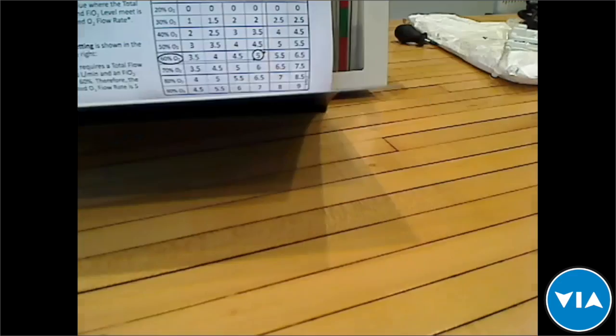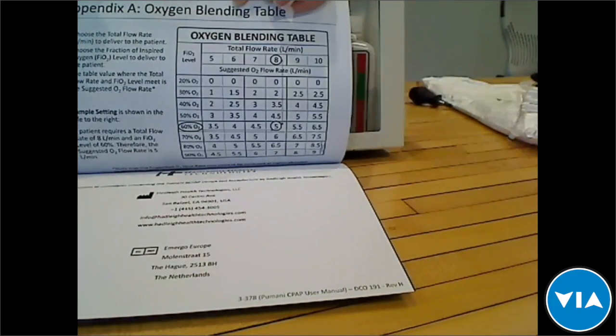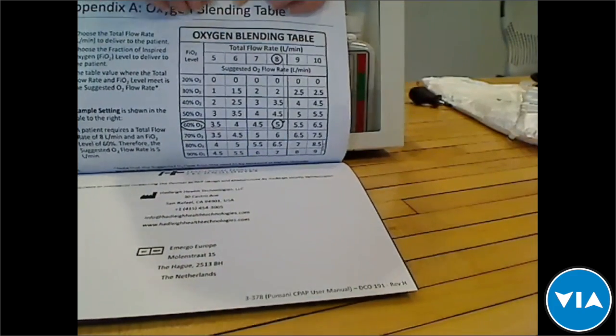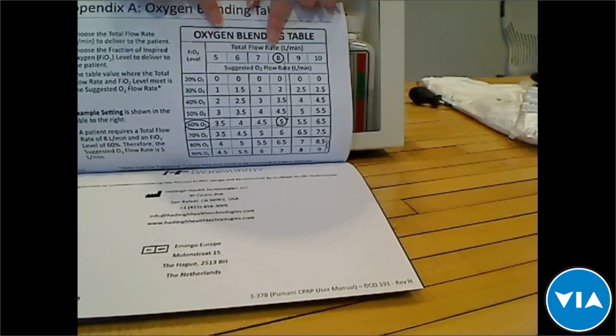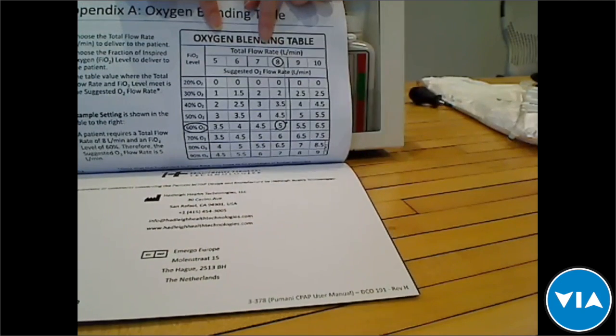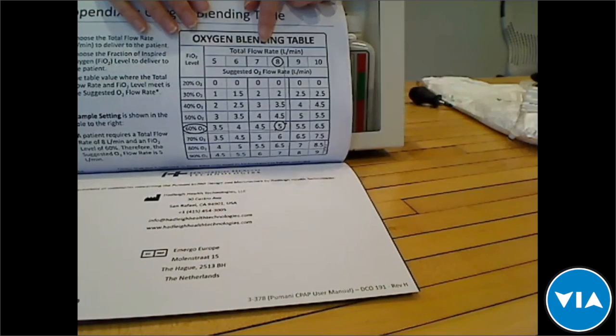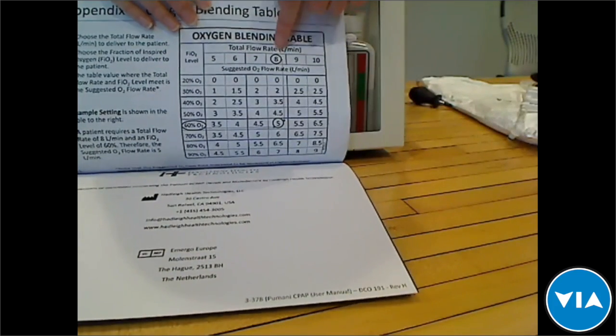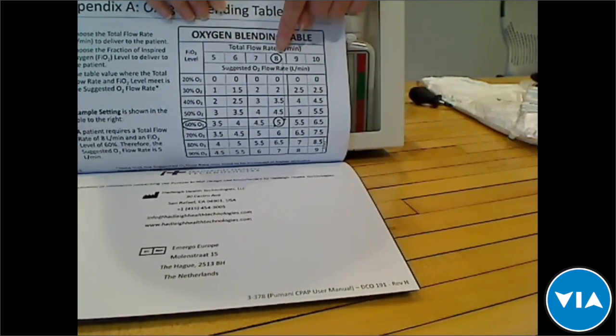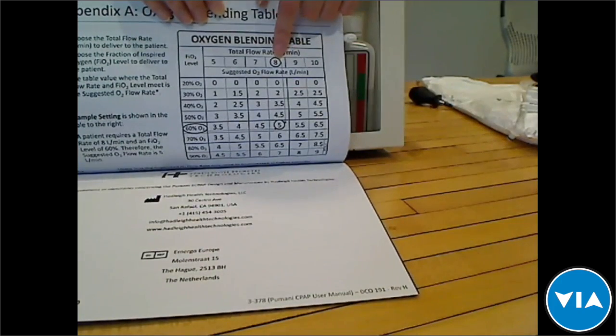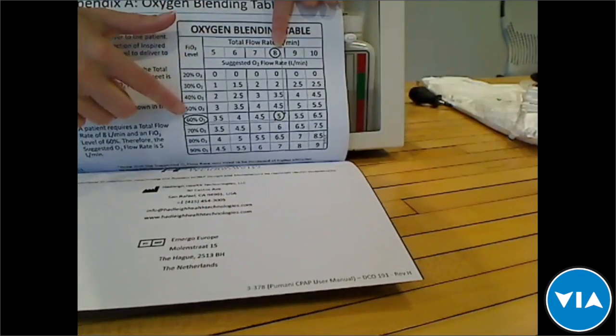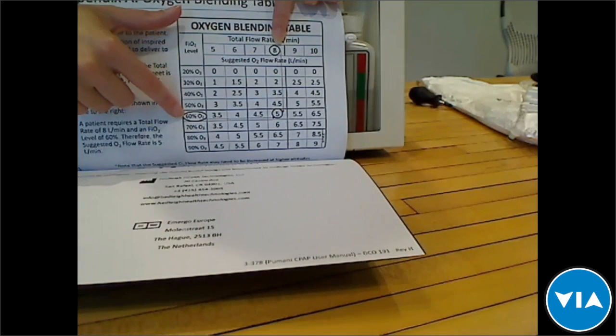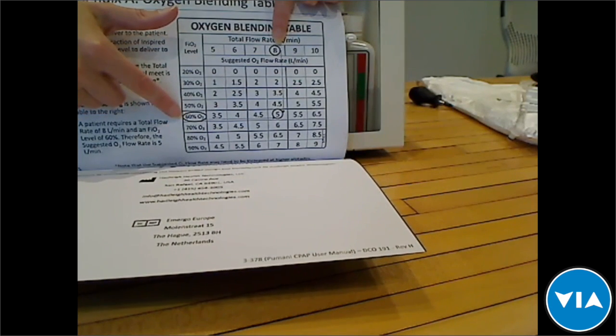So this table is on top of the machine, and we also have a table in the manual. How this works, essentially, in this example: at the top you would choose what your total flow rate should be. That's the amount of air being delivered to the baby. So we'll say for this example that we want the baby to receive 8 liters of total flow, and we would like them to receive 60% oxygen, or 60% FiO2.